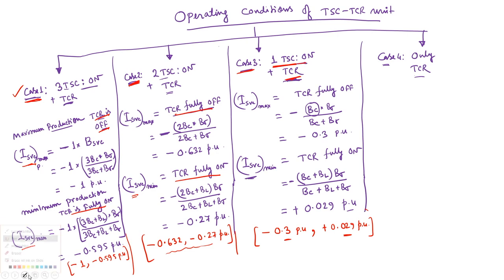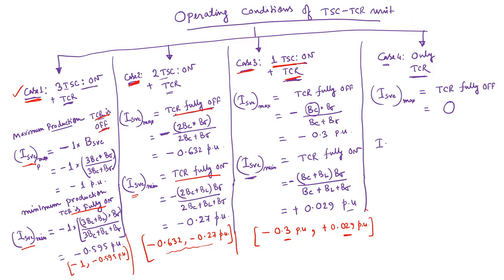Now let us come to the last case, when only TCR will be operational. In that case, ISVC max will be equal to zero when TCR is fully off, since ideally it has zero current, although there will be some VAR absorption due to the susceptance of the step-down transformer, but let us ignore it. So then it will be zero, and ISVC min corresponds to TCR fully on.